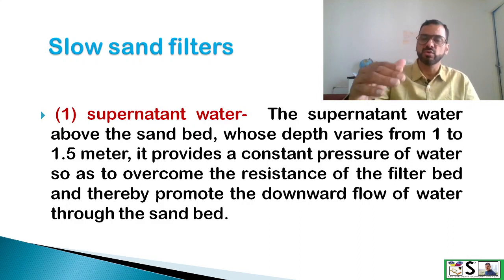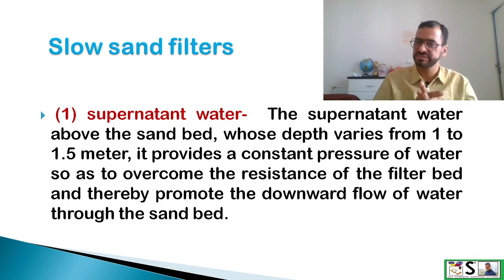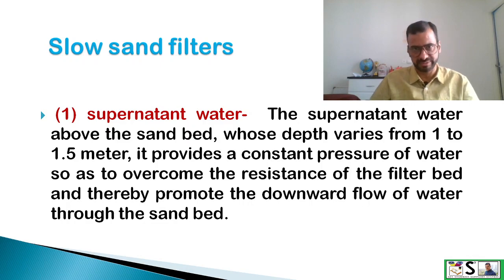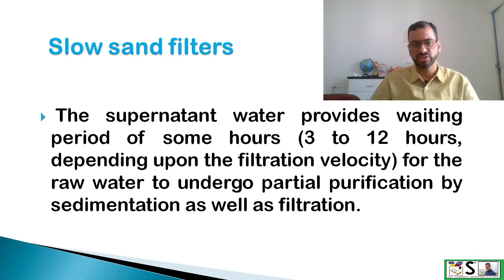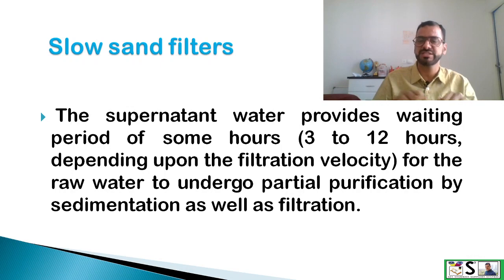The depth of supernatant water is normally kept at 1 to 1.5 meters and remains constant. It provides a constant pressure on the water to filter down, overcoming the resistance of the filter bed and promoting downward flow through the sand bed. It also provides a waiting period of 3 to 12 hours for partial purification by sedimentation and filtration.